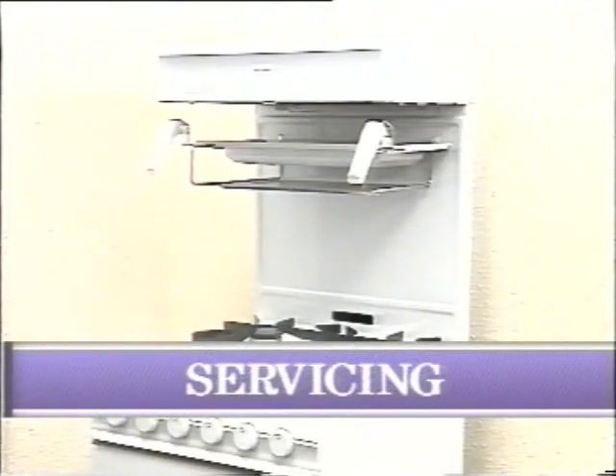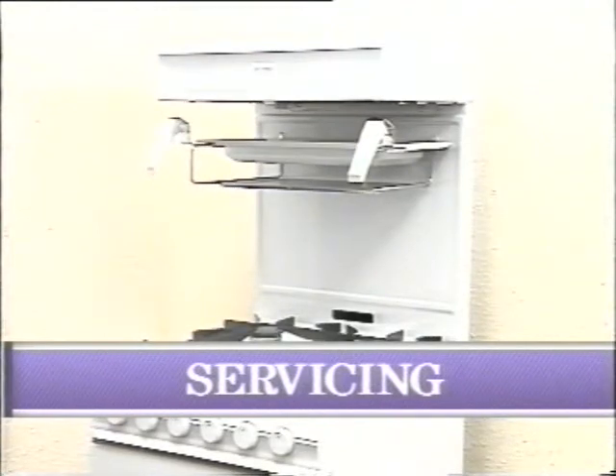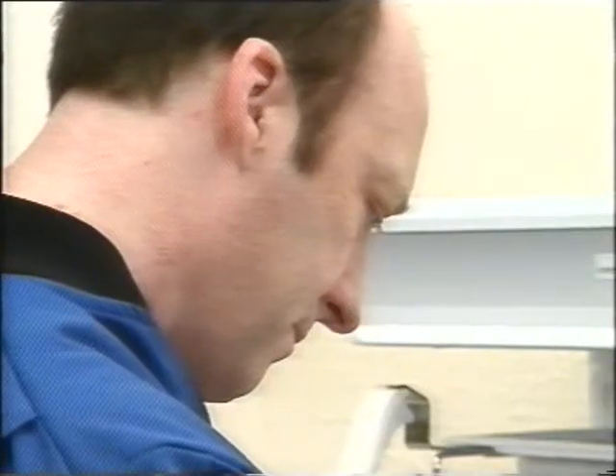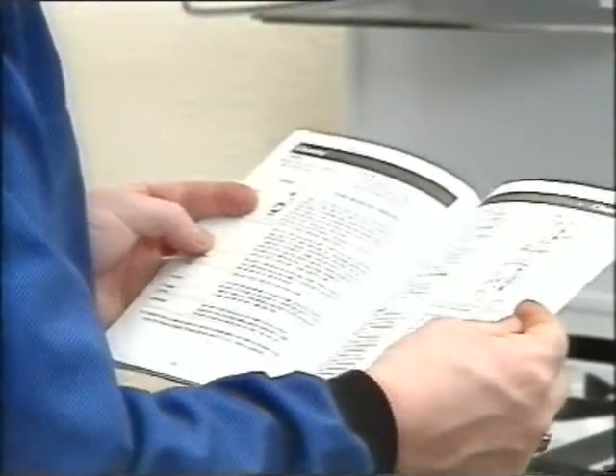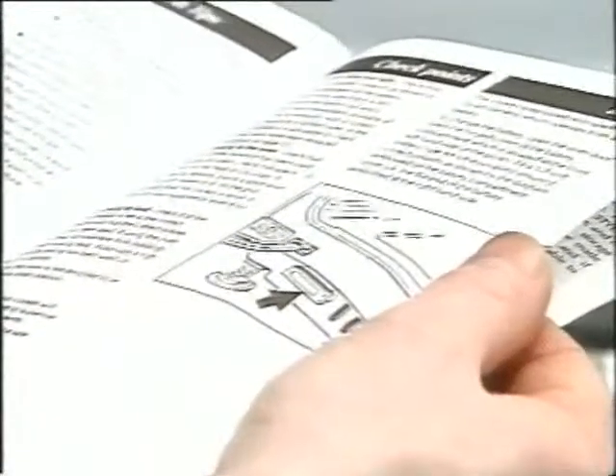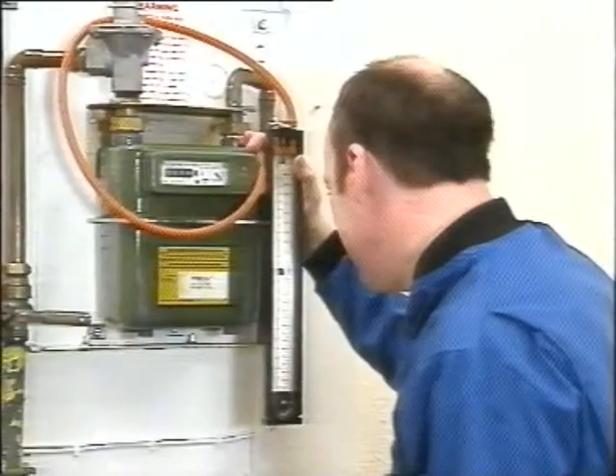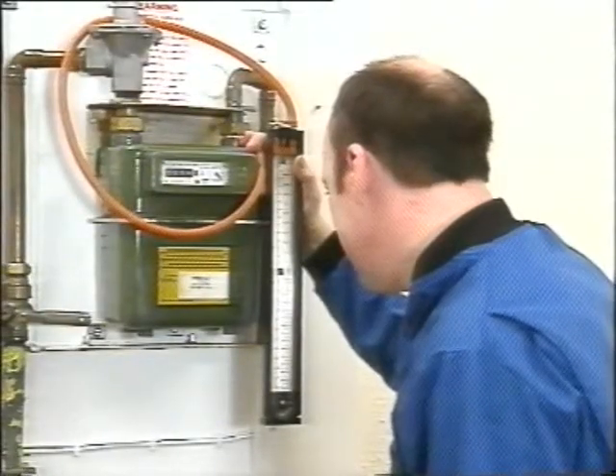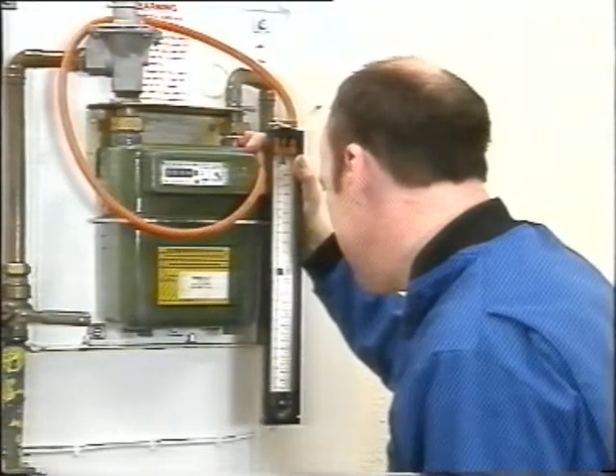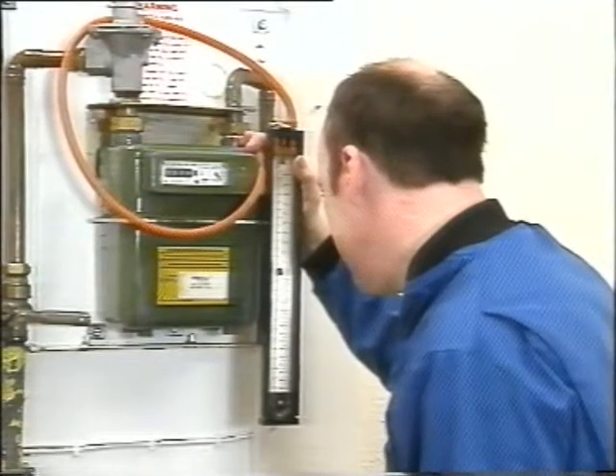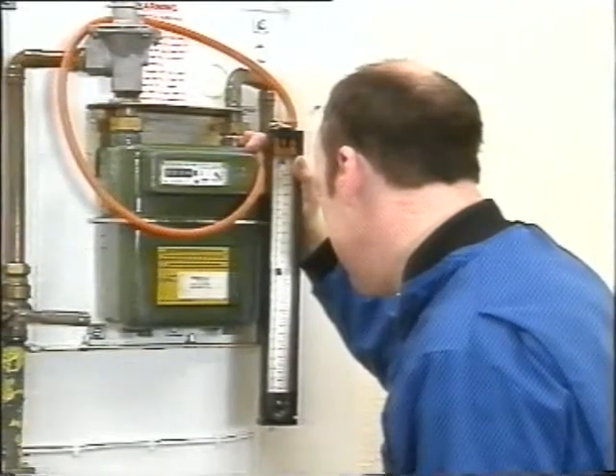Appliances should be serviced at least once a year. The best way of making sure you do a proper service is to follow the manufacturer's instructions. But if they're not available, here's a general sequence to follow. First, clear the work area and put down dust sheets. Before you do anything else, test the gas installation for soundness. Examine the appliance thoroughly and ask the customer how it's been performing.